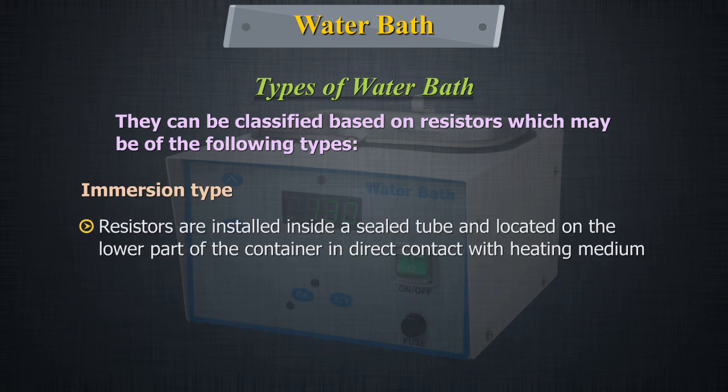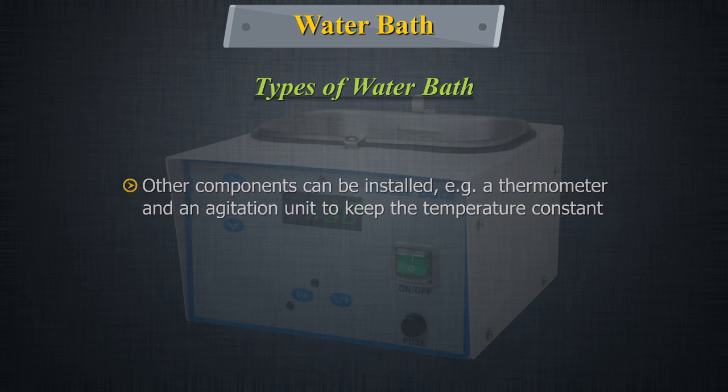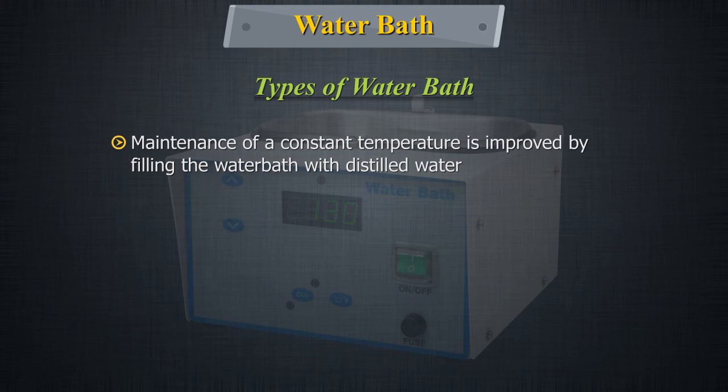In the immersion type, the resistors are installed inside a sealed tube and located on the lower part of the container in direct contact with the heating medium. Other components can be installed, for example a thermometer and an agitation unit to keep the temperature constant.